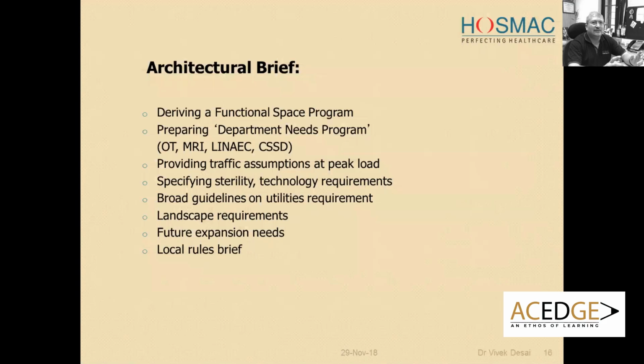We also need to know a little about broad guidelines on engineering—that there are certain norms about sterility, and you cannot enter certain areas freely. For an operation theater, it should go dirty, semi-sterile, sterile. You enter with street clothes, go into change rooms, change, come into the semi-sterile pre and post operative area, then before entering the operation theater there's another change of slippers, and then you get in. So it's dirty, semi-sterile, sterile, and when the reverse happens it also has to follow the same path—it cannot happen that sterile mixes directly with dirty. That kind of sterility requirement will be there, which you need to know.